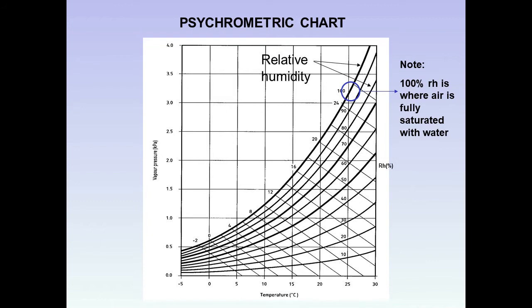The scale on the left is vapor pressure. So let's imagine that the temperature and relative humidity recorded were 60% RH at 20 degrees. There's our 60% RH line and 20 degrees at the bottom, and where those two meet we put a mark.